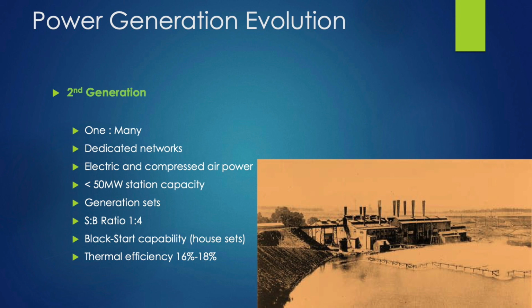Second generation power stations use compressed air, power station capacity less than 50 megawatts. They use generating sets, and the generating set is basically a turbine and a generator combined. They had far more boilers. The ratio between sets and boilers was 1:4. Very important to understand is that much of your maintenance capacity sat in the boiler design. They knew boilers were far less reliable than generating sets, so you had many boilers. While one has broken down on a tube leak, they're repairing that and using another in a common steam range, and the power station can just keep on going.